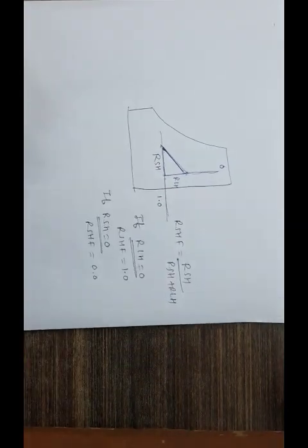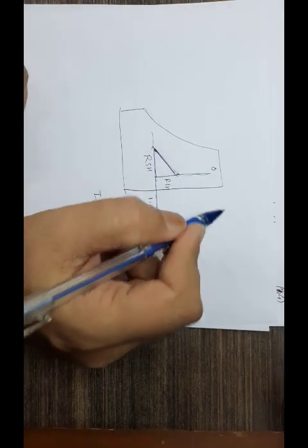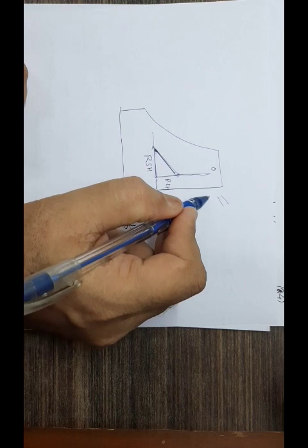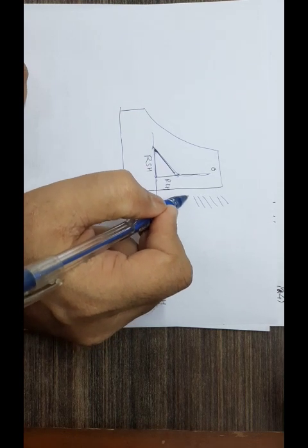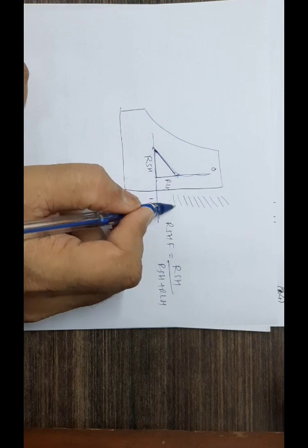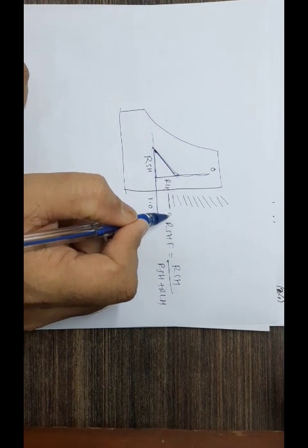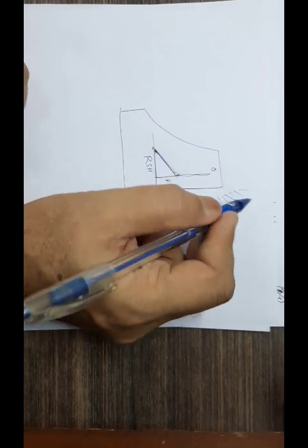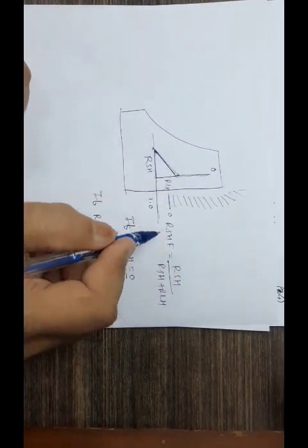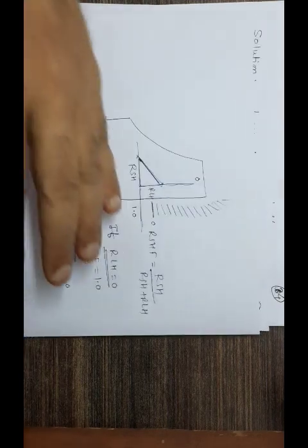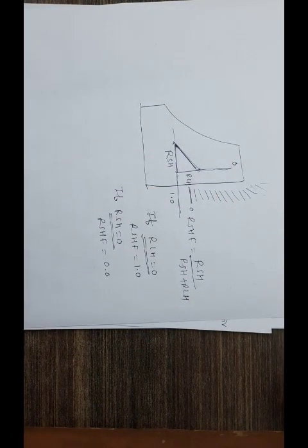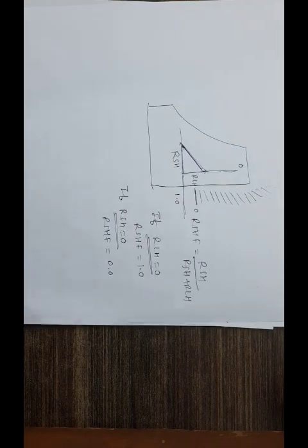If you go back to the psychrometric chart, you will find that there are some additional lines provided here, of different slopes, and then gradually the slope starts reducing and then it becomes horizontal. If you go further here, the slope will go on increasing and it can actually become 1, but they don't show it up to 1 because that's not practicable. So from 0 gradually, these lines have more and more slope. So these are constant RSHF lines. I'll just show you that in the actual psychrometric chart.